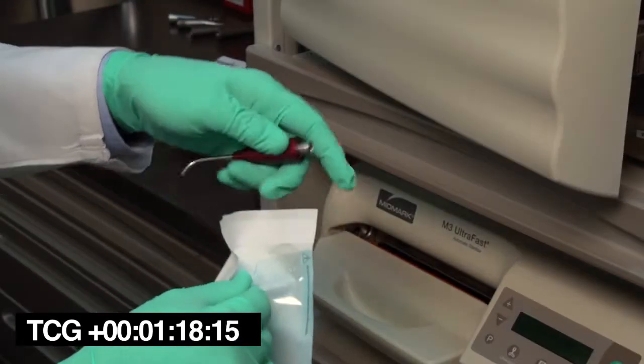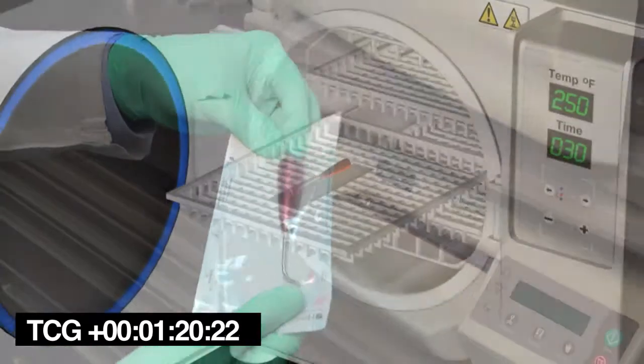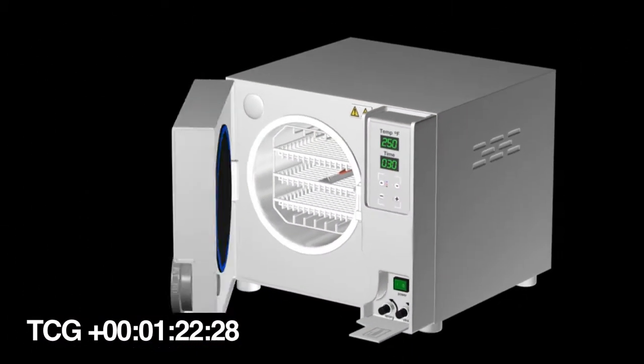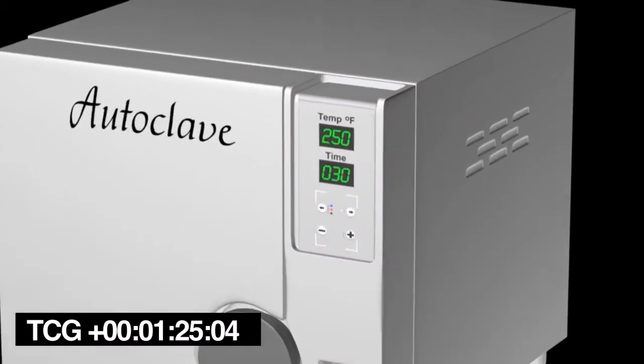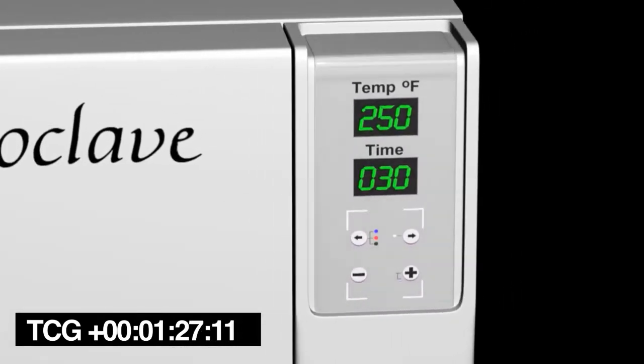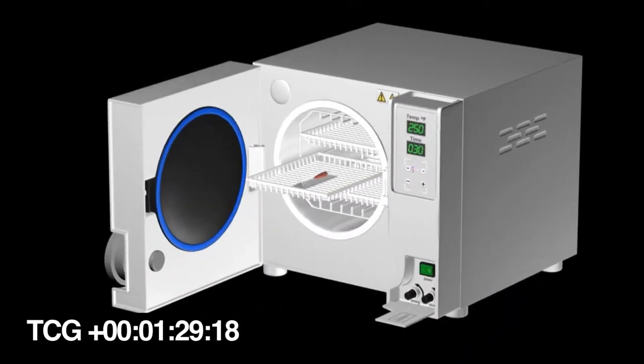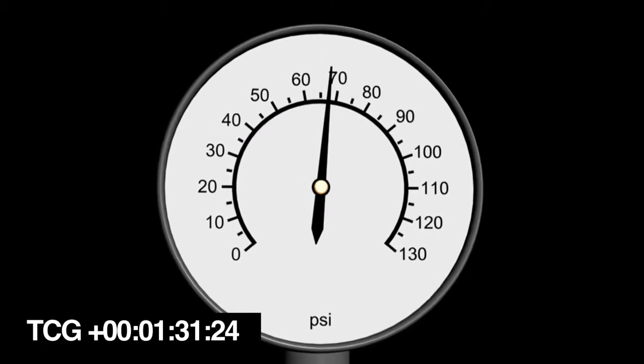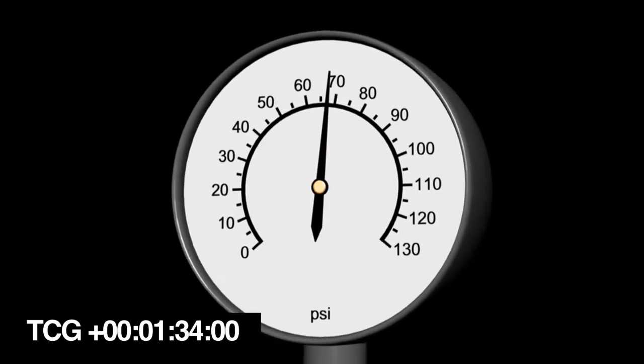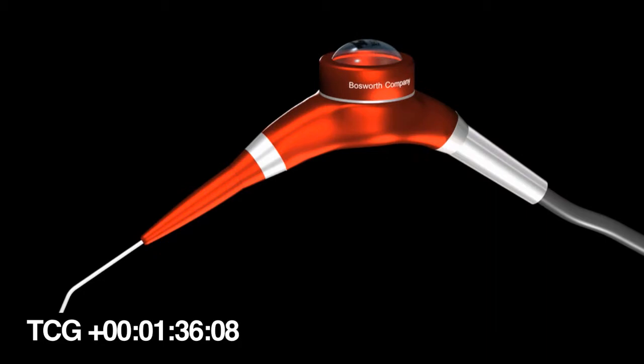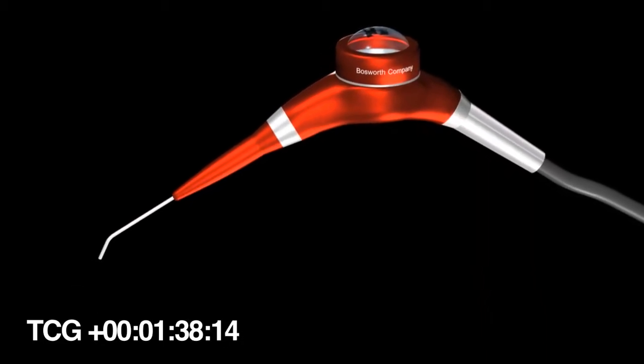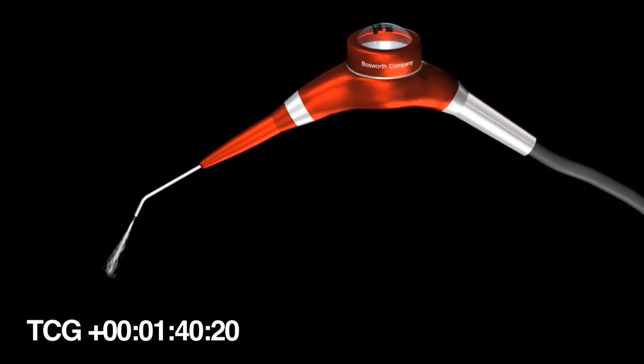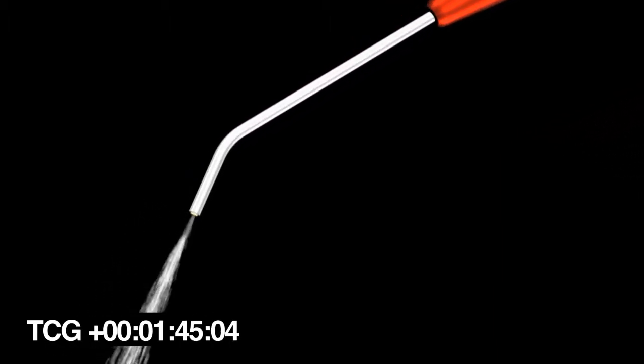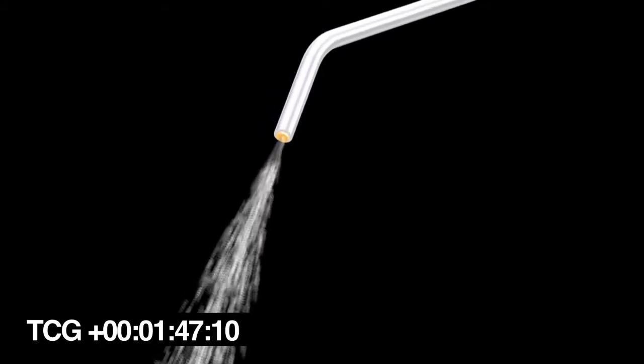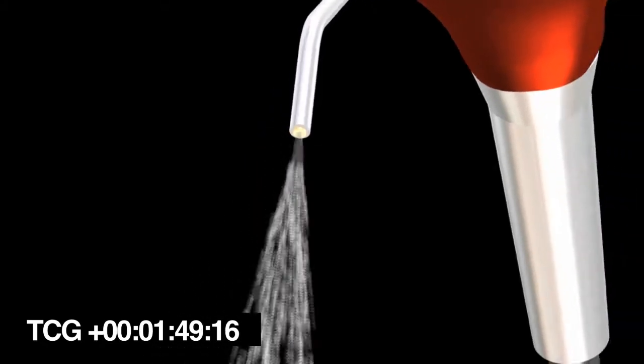Sterilize the nozzle prior to first use by autoclaving at 121 degrees Celsius, 250 degrees Fahrenheit for 30 minutes and allow the nozzle to dry for 15 minutes. Set the dental delivery unit's air pressure to 65 to 70 psi. When set to the correct air pressure, the unit will emit a steady stream of air, water, and Prophy powder. This is optimum in order to operate the air polisher properly and to avoid clogging.